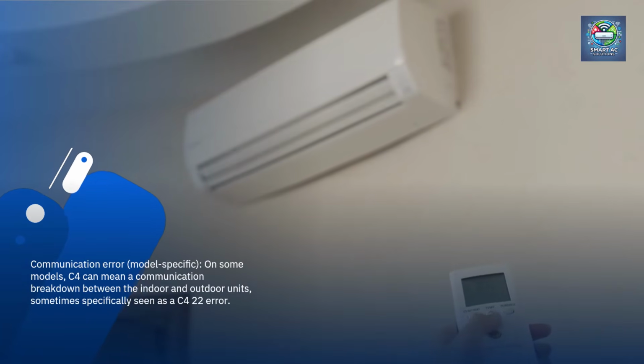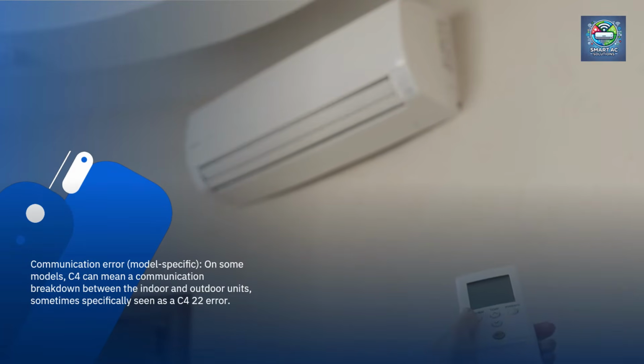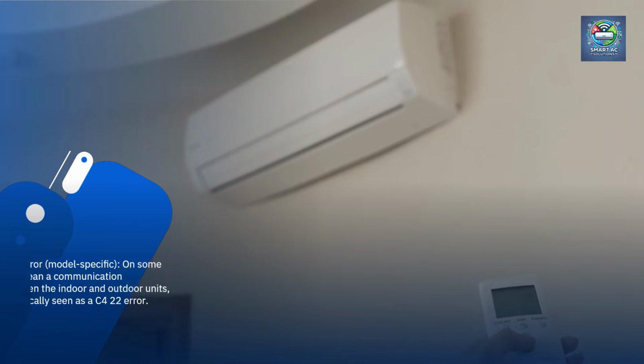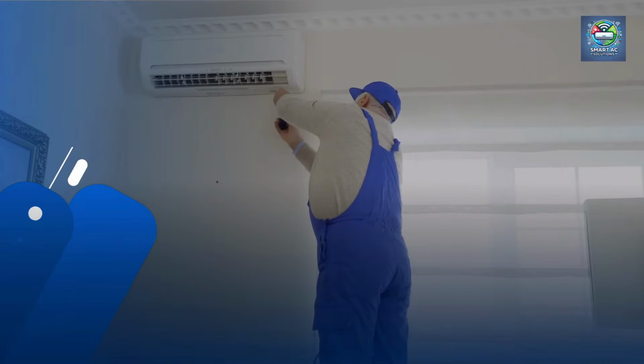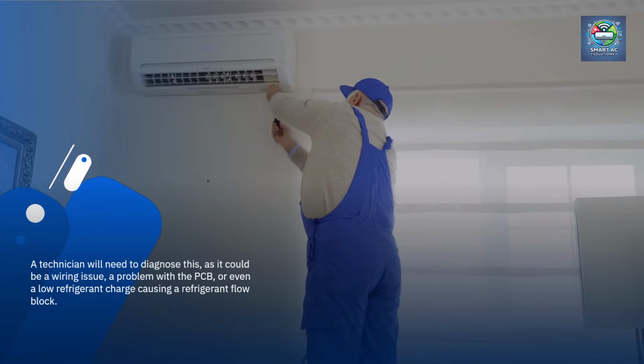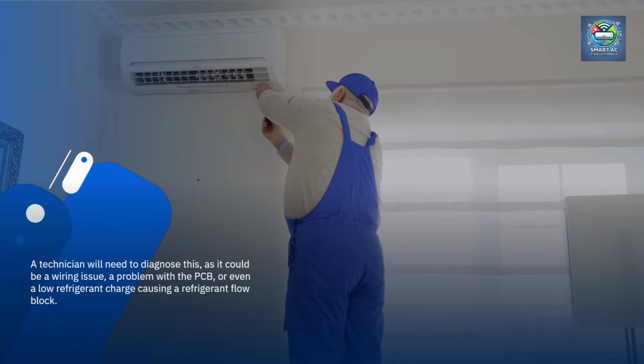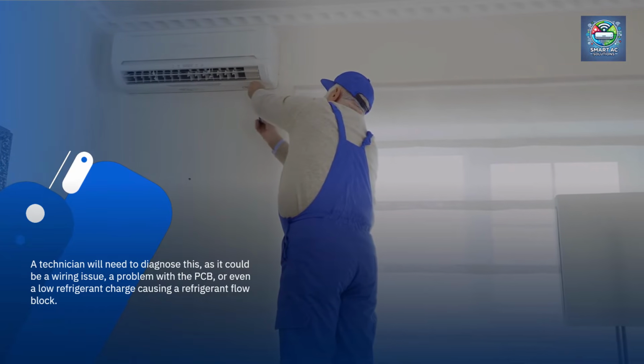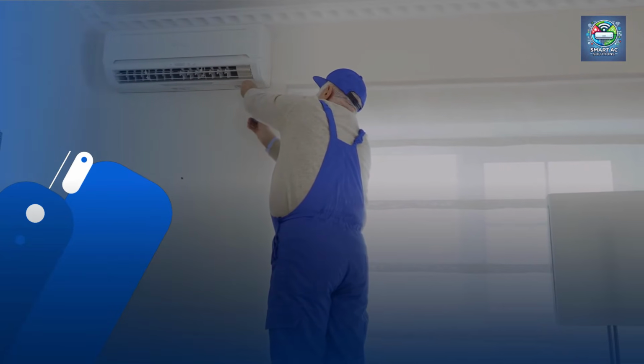On some models, C4 can mean a communication breakdown between the indoor and outdoor units, sometimes specifically seen as a C422 error. A technician will need to diagnose this, as it could be a wiring issue, a problem with the PCB, or even a low refrigerant charge causing a refrigerant flow block.